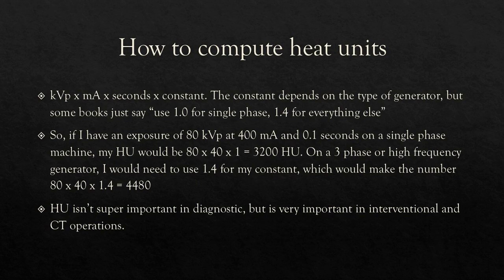If I swap that out to a three-phase generator or high frequency, I use the constant of 1.4. So 80 KVP times 40 MAS times 1.4 gives me 4,480 heat units. With more efficient equipment you do generate more heat at the anode, but that's okay because the anodes are designed to handle that additional heat, and it's really good for the patient because your x-ray output is much more consistent and your images are better.